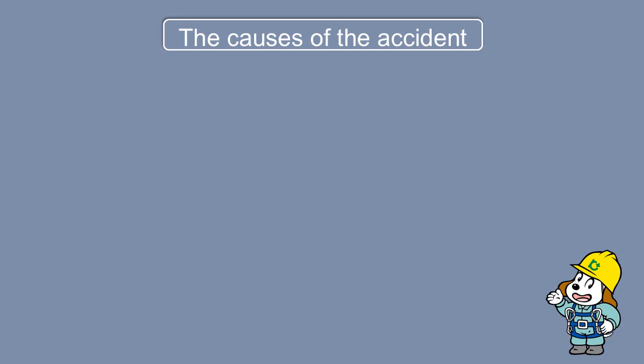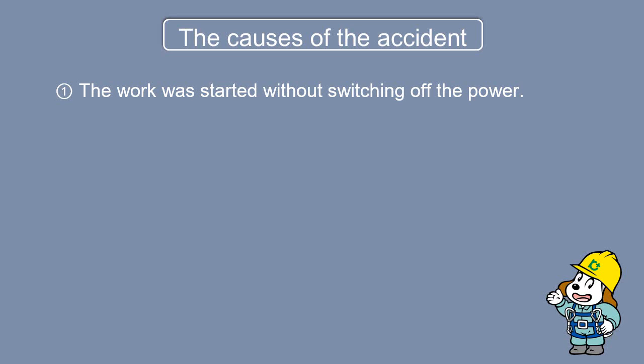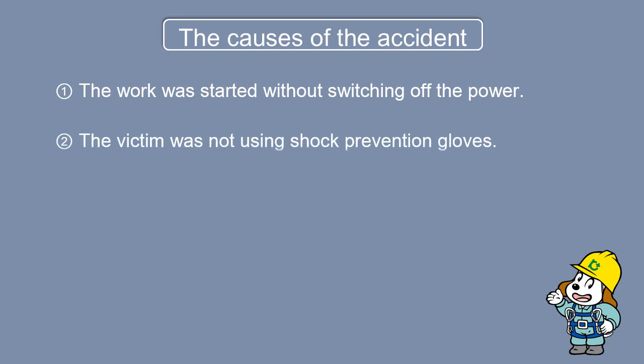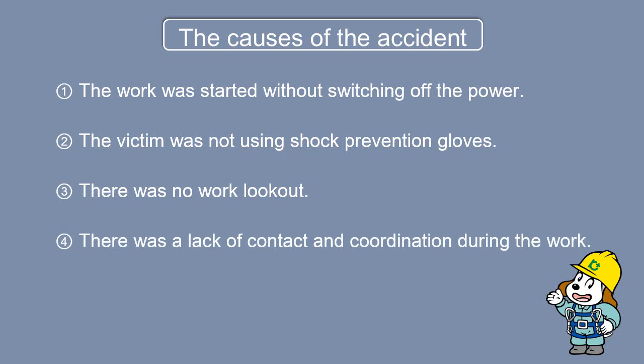The causes of the accident. The work was started without switching off the power. The victim was not using shock prevention gloves. There was no work lookout. There was a lack of contact and coordination during the work.